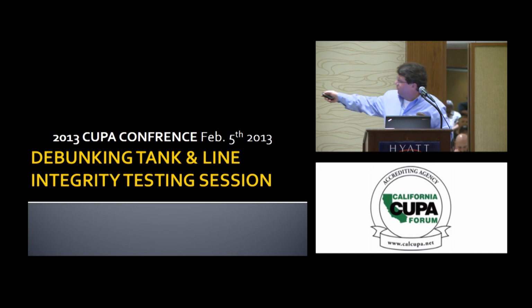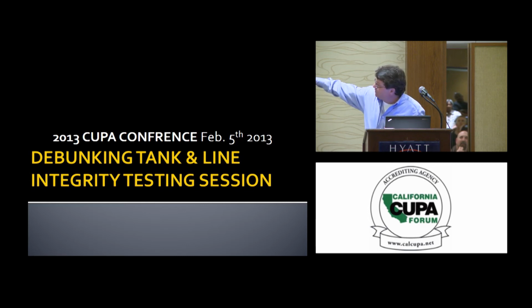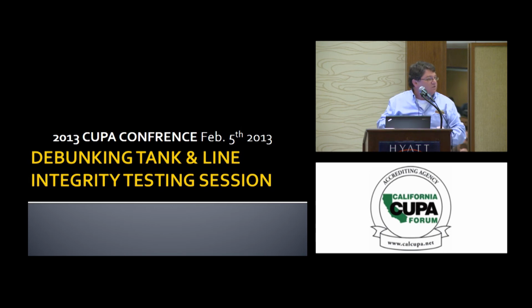If you can see this one right here that I'm putting the laser on, do you see that crimp right there? It's very hard to see. It's right past the fitting, right where my laser is. That's a crimp. That is the beginning of a deterioration of that flex connector. That is the beginning of the end of that flex connector.